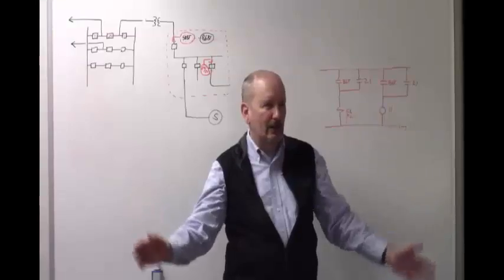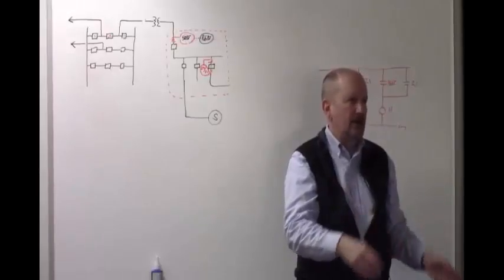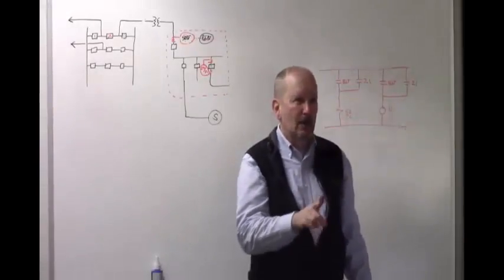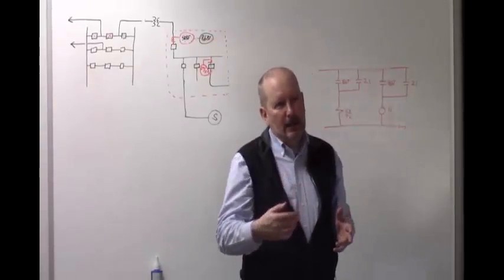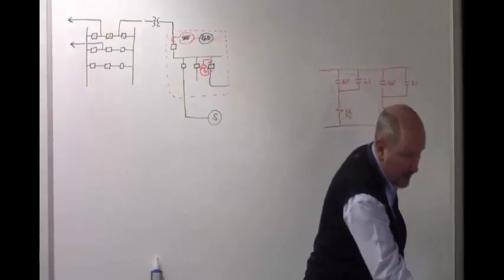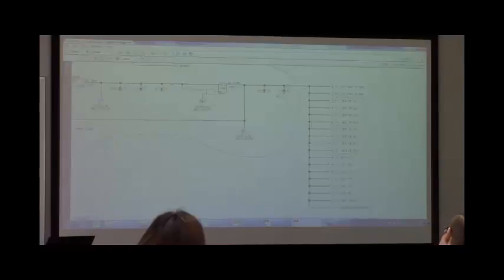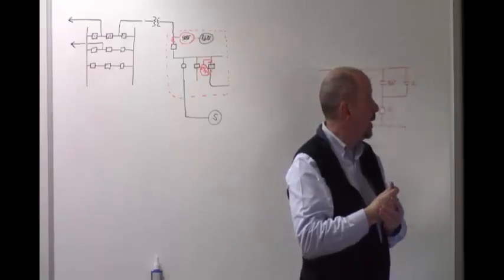When a breaker failure scheme operates, it happens faster than human perception — the whole thing is over in about 10 to 12 cycles. There are also LED indicators on the front face of the relay visible in the logic diagram; most of them are used for testing the device rather than operational indication.